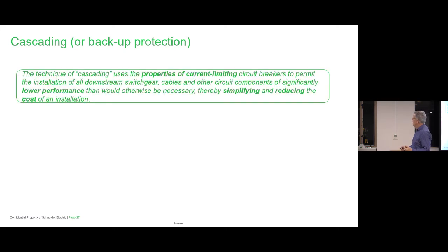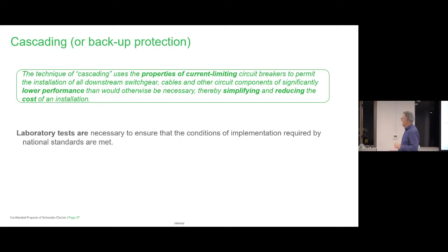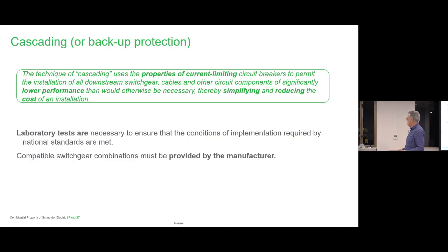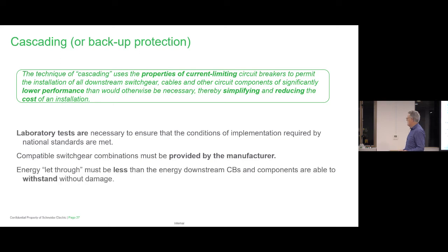So this is a technique using properties of current limiting, what we just talked about, to permit the installation of downstream switchgear, cables and other circuit breakers of significantly lower performance than otherwise necessary. That means by having a good selection of breaker upstream with that ability, we can put in a lower value fault level breaker downstream. This is what we were able to achieve. Of course, we can't just do it. We're talking about big energy here. It's got to be tested. A compatible switchgear combination must be provided by us, and the energy let through must be less than the energy withstand of the downstream circuit breakers. That's that energy information that we were telling you about.